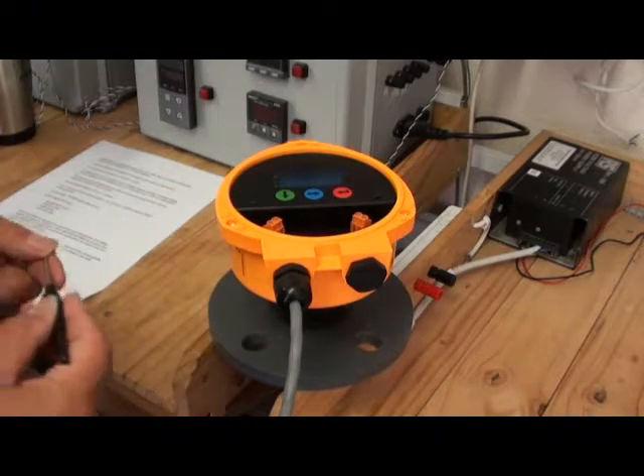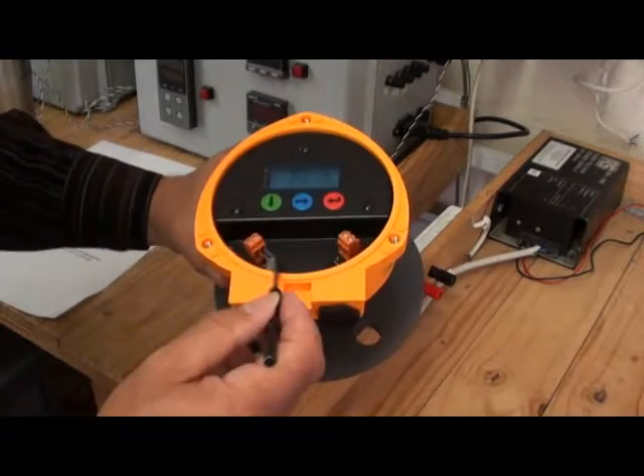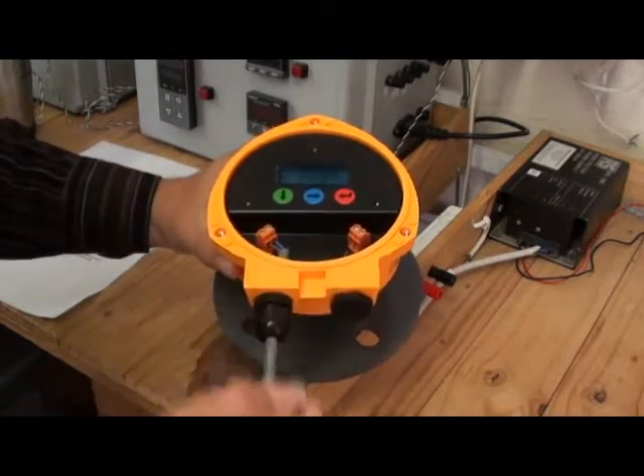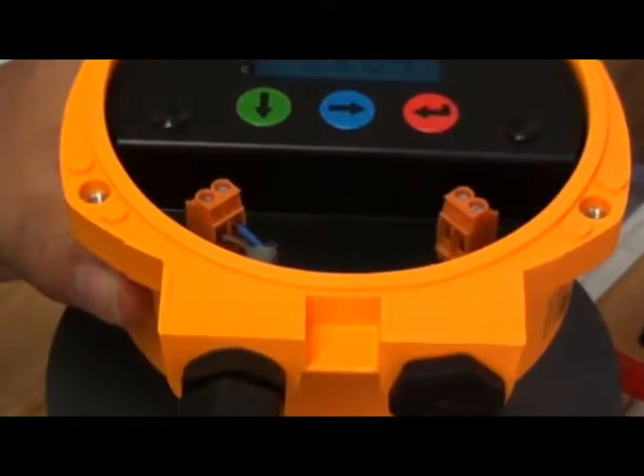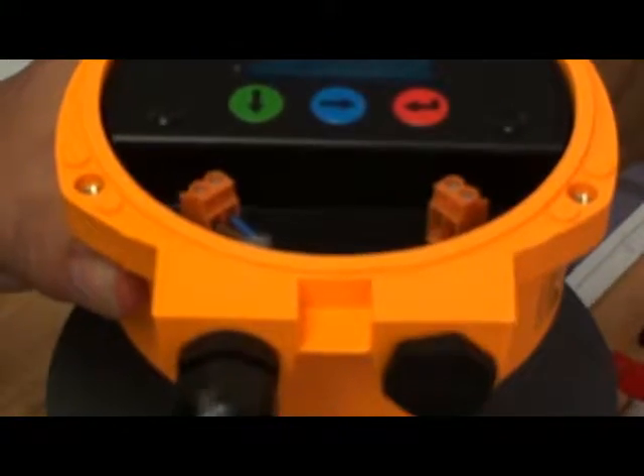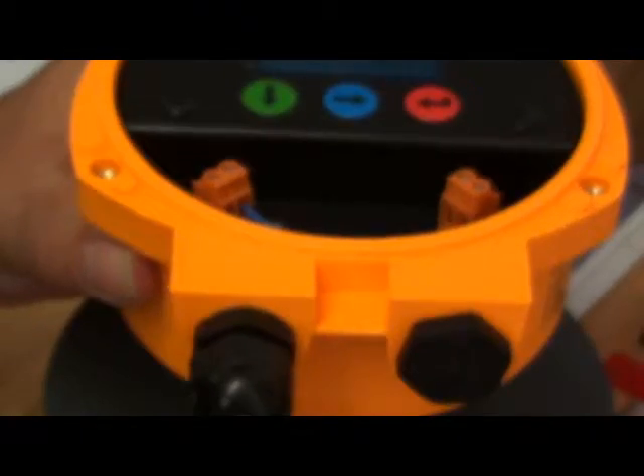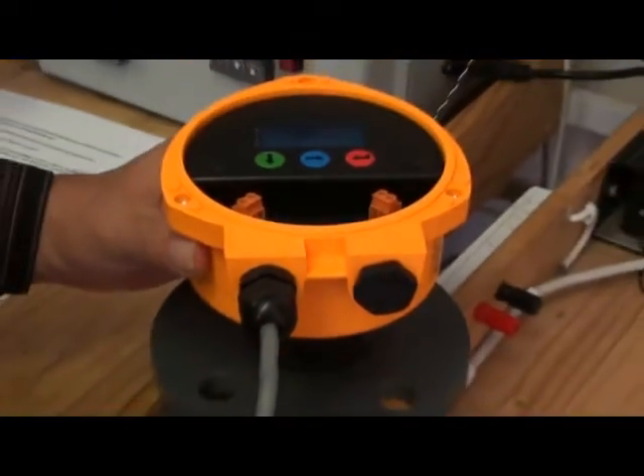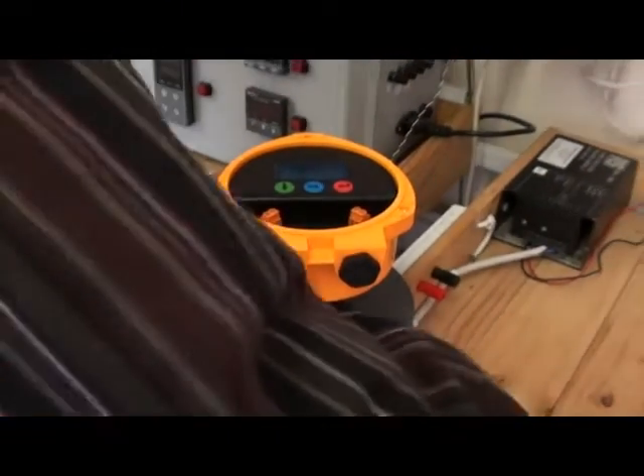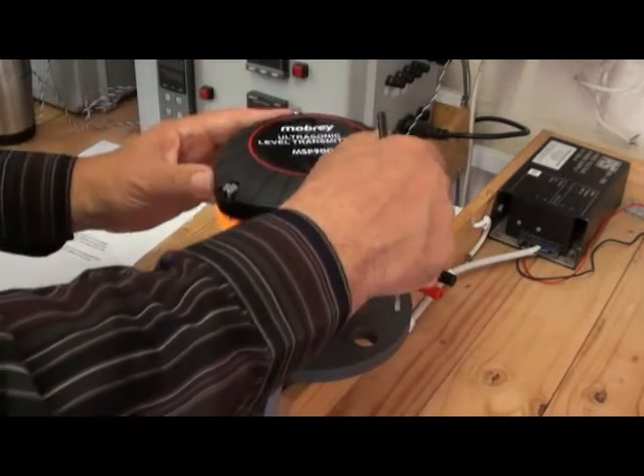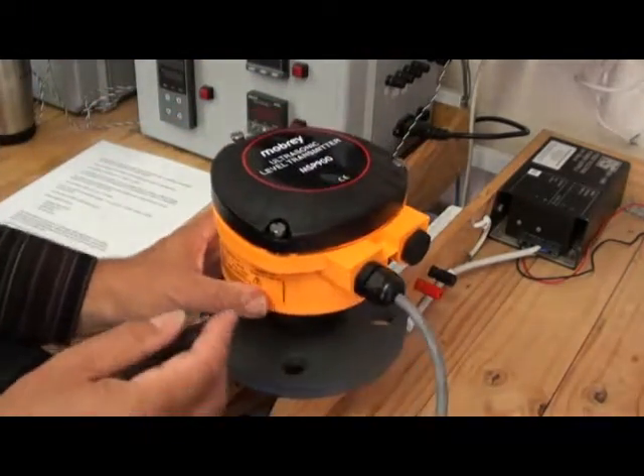It is a 2-wire loop powered system, 12 to 30 volt DC with a 4 to 20 milliamp output and HART communication. The housing is IP66/IP67 glass nylon.